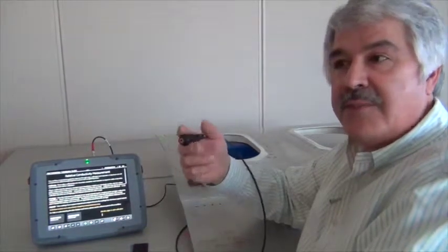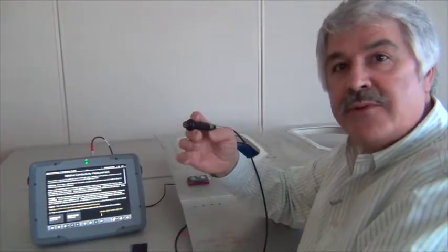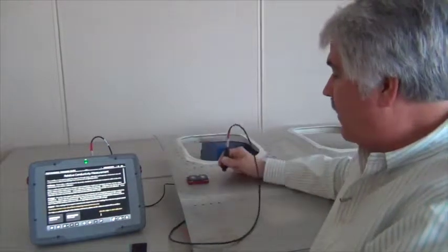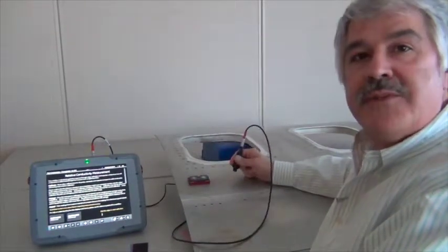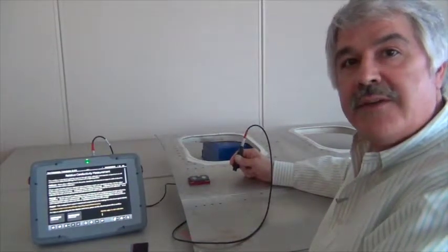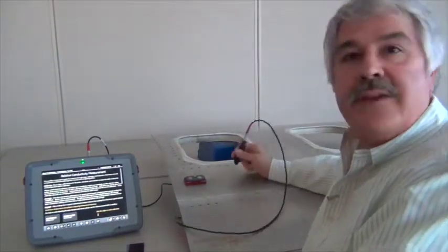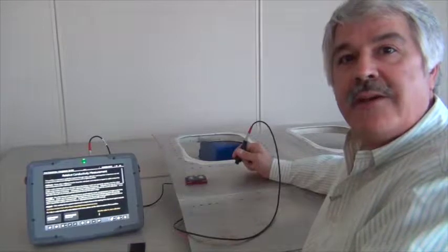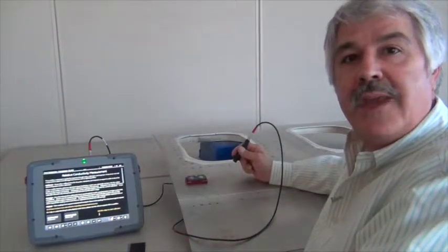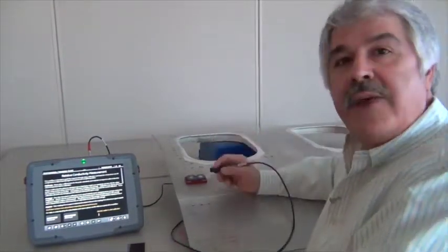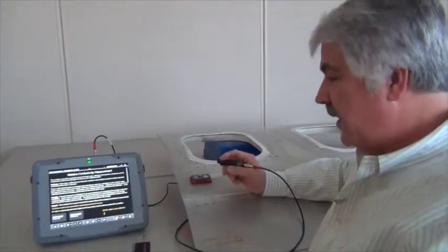That is, first step is to calibrate against a known standard. The second step, as spelled out in the number of inspection procedures, is to acquire a number of measurements from known good areas of the product under test. And the third step then is to go take measurements of suspect areas, comparing those against the averages. So I'll walk you through how that all works on the Mentor.